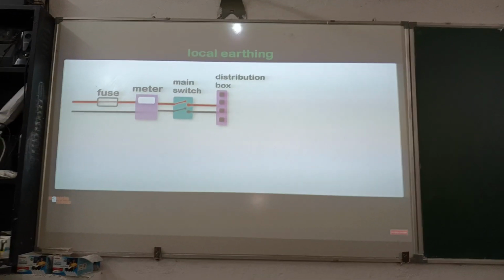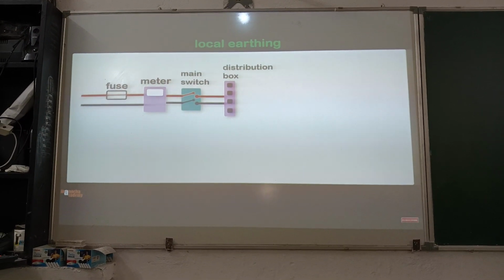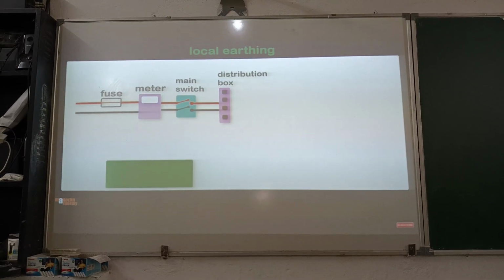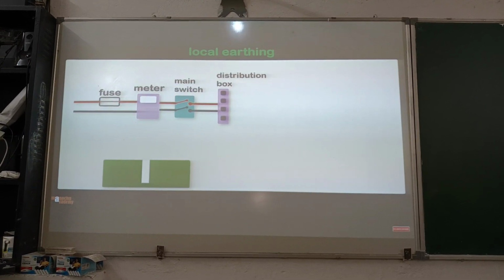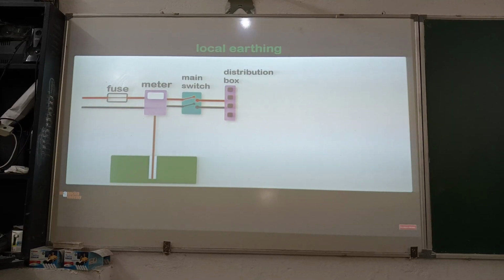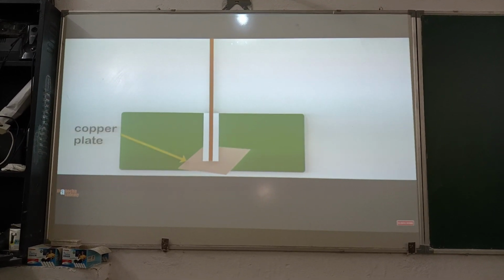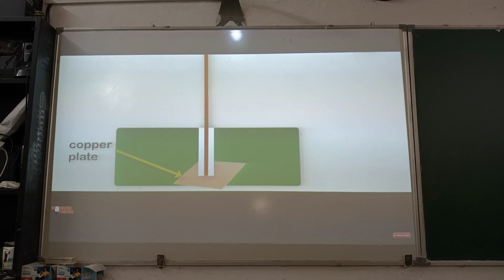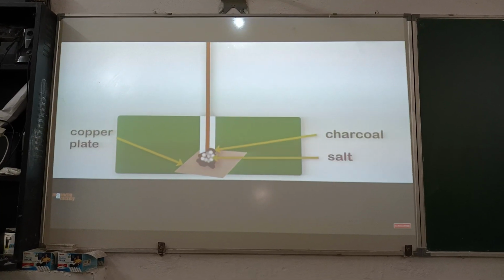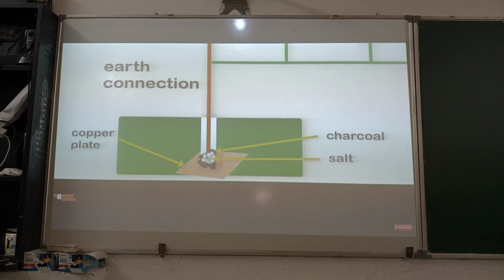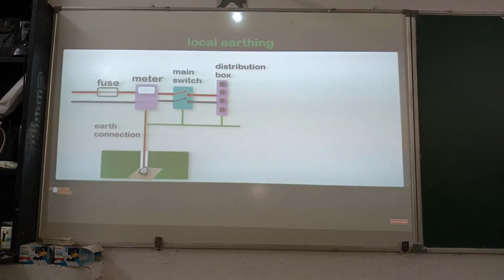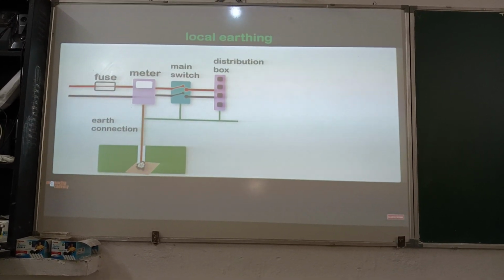The earth connection, or local earthing, is done near the electricity meter. A hole about 2 to 3 meters deep is dug, and a copper rod with a thick copper plate at its end is inserted and buried. The plate is surrounded by a mixture of charcoal and salt to make good contact with the earth. The upper end of the rod is joined to the earth connection at the electricity meter.